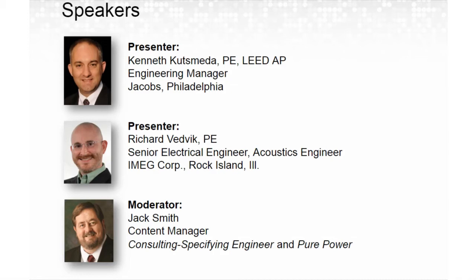Yeah, and I think when you talk about architecture, having breakers that are fully adjustable can help with the arc flash. We talked about PDU losses and eliminating the PDU to eliminate the transformer losses, but that has an adverse effect on the short circuit. So these are just things you need to look at in how you build the architecture. In that case, we tend to build smaller architectures, smaller transformers, so we have less fault current. So I agree with Rich, it does affect how the architecture is built.